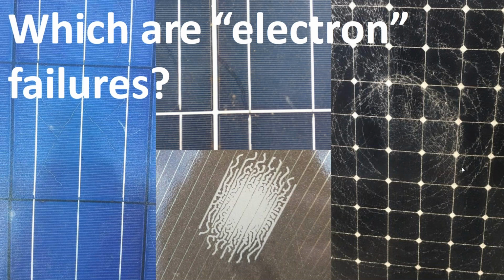And so now we're getting into a real advanced issue that solar installers don't quite understand, which are called snail trails. They kind of look like little slug lines, like a slug has just crawled across your solar array.